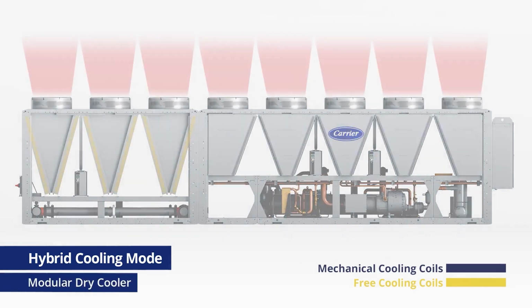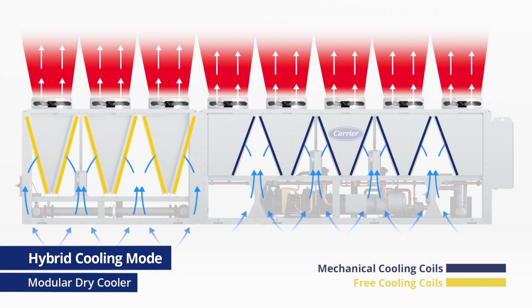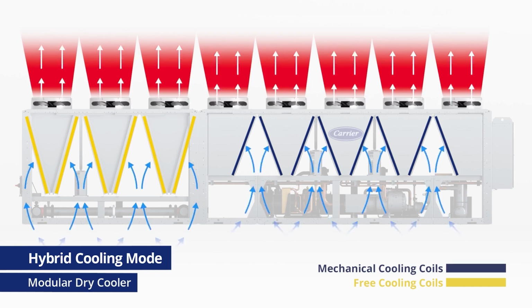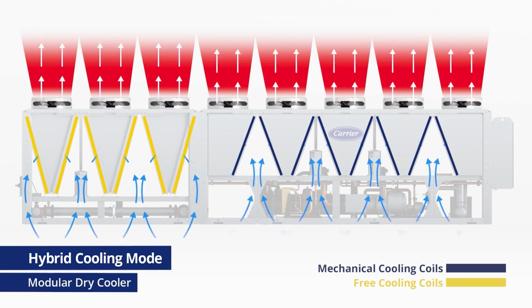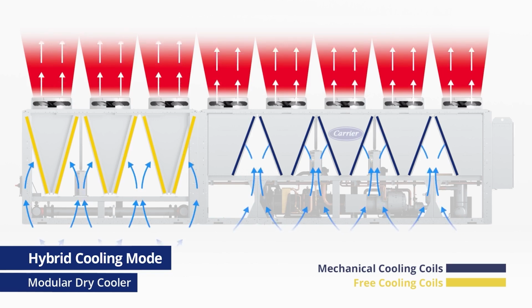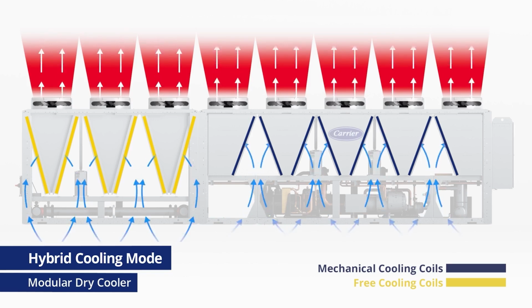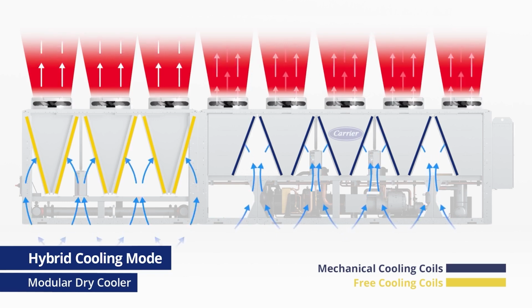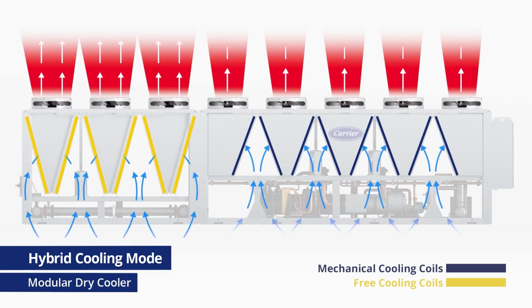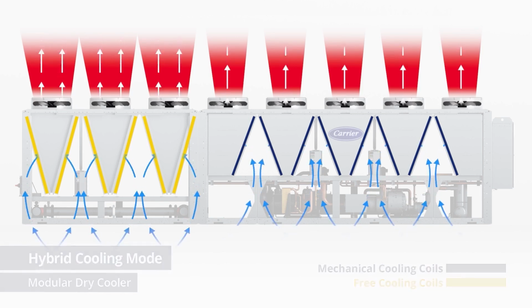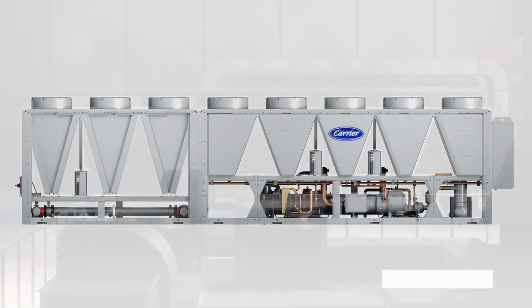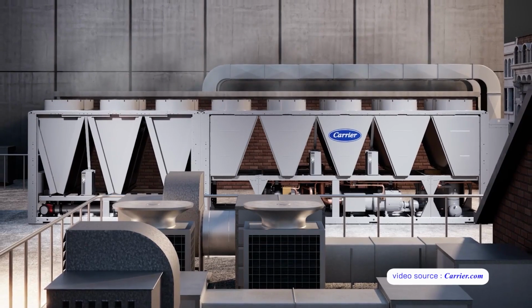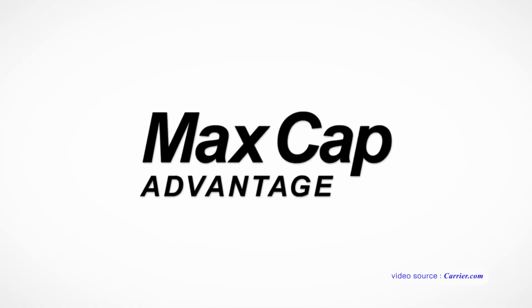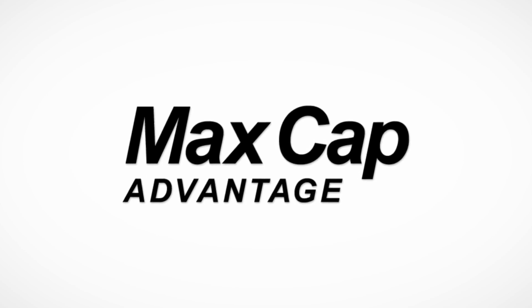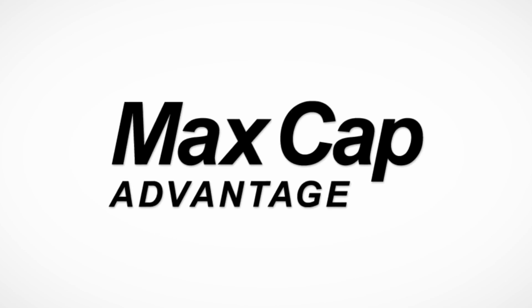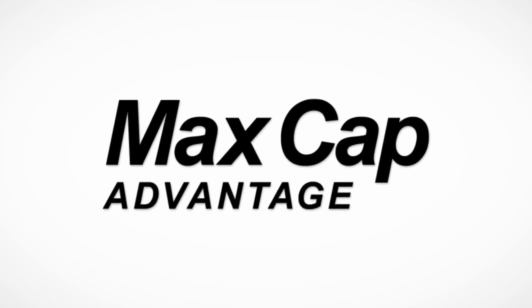In the modular design, the mechanical and free cooling sections are able to operate independently. So, in hybrid cooling mode, the air flows over the mechanical and free cooling coils separately. This allows the free cooling fans to speed up, extracting every bit of free cooling possible. At the same time, the mechanical cooling fans can slow down, maintaining set point and protecting the system, and again, saving energy. The result of these Carrier operational benefits is known as Max Cap Advantage. In short, this allows the owner to maximize free cooling benefits across all operating conditions, maximizing your energy savings.